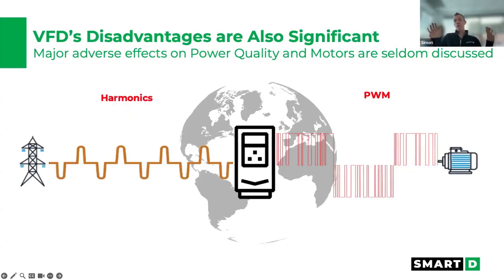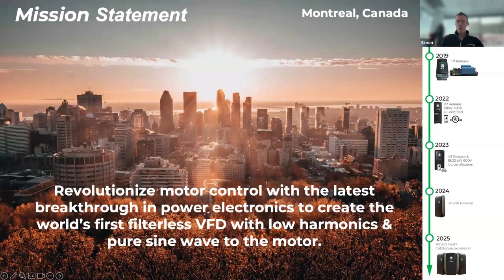And we can put those into two broad categories: impacts on the grid, mainly harmonics, and impacts on the motor coming from the pulse width modulation, as you've seen in the quick video. And SmartD's mission, really, since our inception in 2018, has been to create a VFD that addresses both the disadvantages on the grid and on the motor. So a truly filterless VFD with low harmonics on the grid and a pure sine wave to the motor.